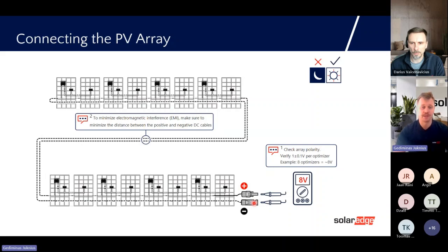And then the last thing is never ever use very cheap multimeters. If you do, it can show you something like 7 volts even though you have 8 optimizers, and you will be trying to find the faulty one, but it's just that there are long cables and your multimeter is not good enough to measure correctly. We always say that there is a deviation from 1 volt. It can be 0.9, it can be 1.1, but it's always going to be approximately 1 volt per optimizer.